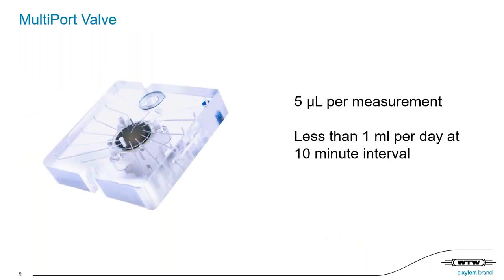Here you see the multiport valve, which is the core part of the analyzer. Within this unit, the sample transport, degassing, and mixing takes place. Thanks to this component, the solution consumption of Alyza is extremely low. For example, the orthophosphate unit uses 5 microliter of reagent per measurement, which means it is using less than 1 milliliter per day with a 10 minutes measuring interval.